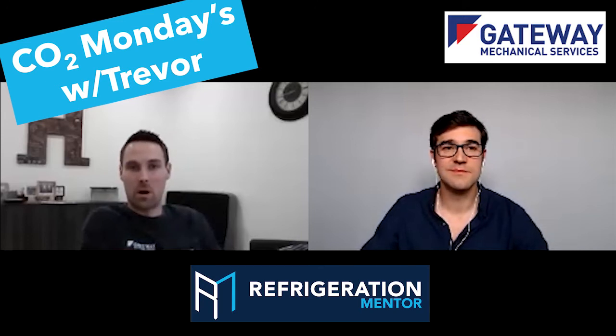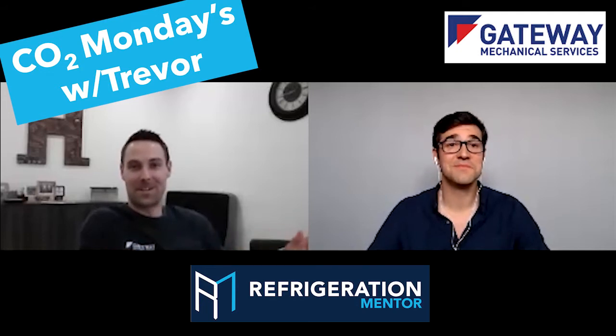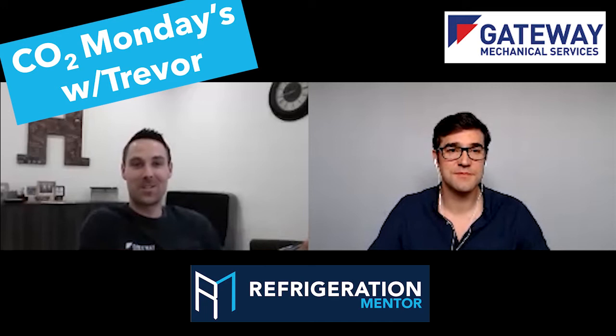And if you get the chance to go to a CO2 store by yourself for the first time, and you think you're getting a little bit thrown into hot water, you know what I tell all the guys? Locate the emergency unit first. Just find where that override switch is. If you accidentally trip the rack off, if you know where that switch is, you can even test it while the system's running. Go and turn it on, make sure that switch works.